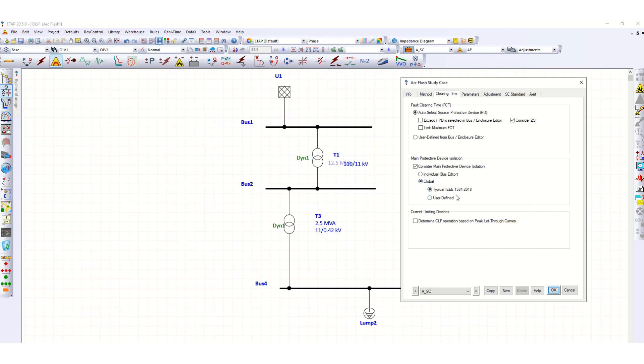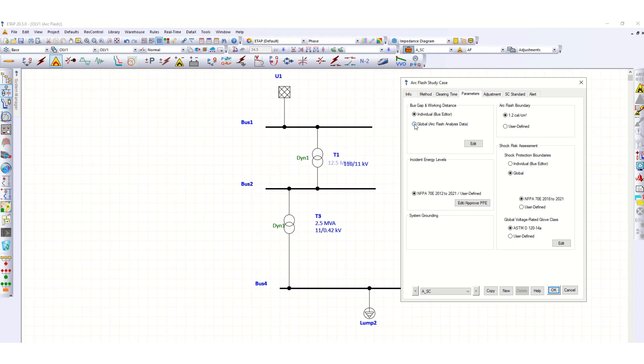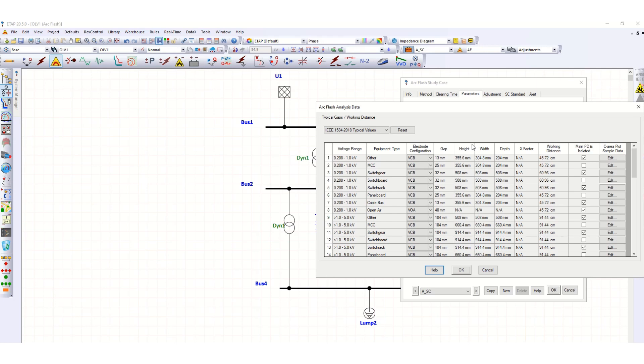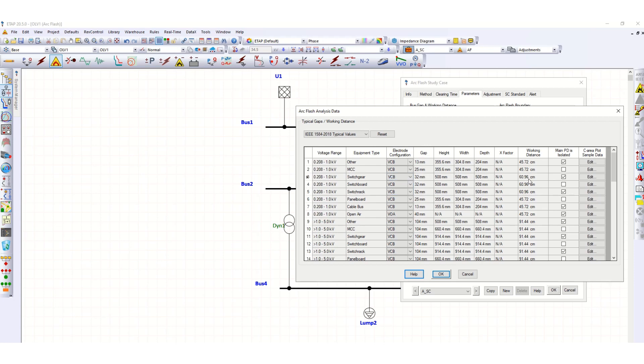Let's check parameters. You can choose bus gap and working distance from individual bus editor or global Arc Flash analysis data. Let's check this one, typical IEEE 1584-2018. Here you can see the typical values for different voltage ranges and equipment types. Suppose this is switchgear, the voltage range up to 1 kV, and this is electrode configuration, whether vertical or horizontal. This is the gap, height, width, depth, and working distance.